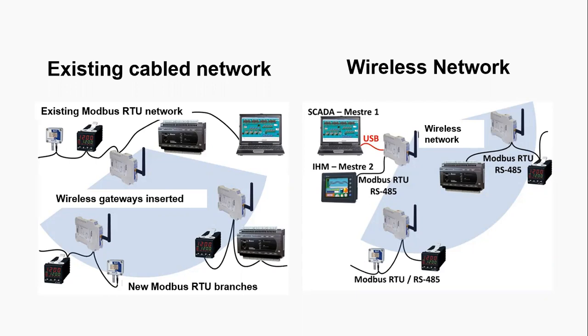Then you should configure the baud rate accordingly, a smaller baud rate for longer distances. Those are the usual RS-485 concerns that we must have. But on wireless, those baud rates don't mean anything. On wireless, it won't affect. So that is important too.